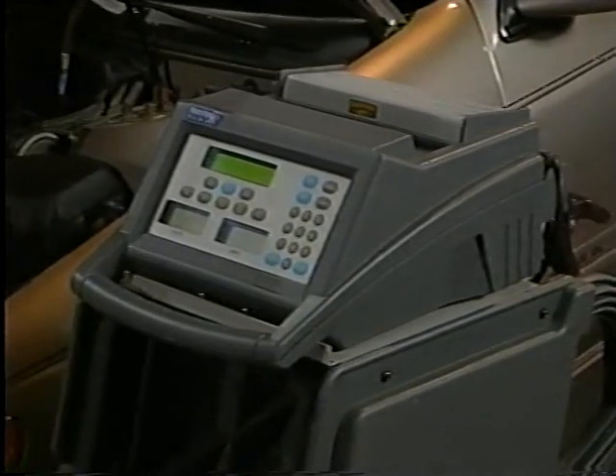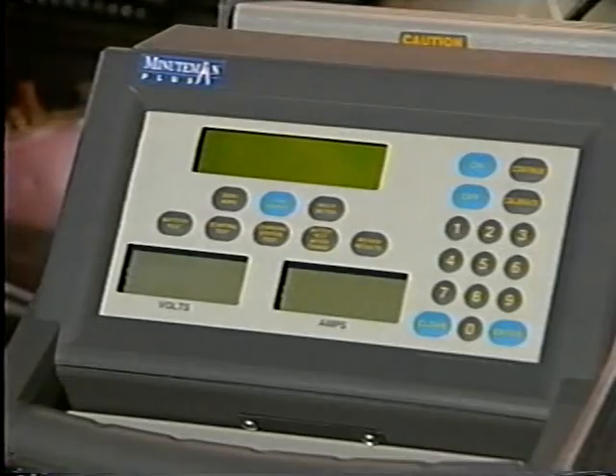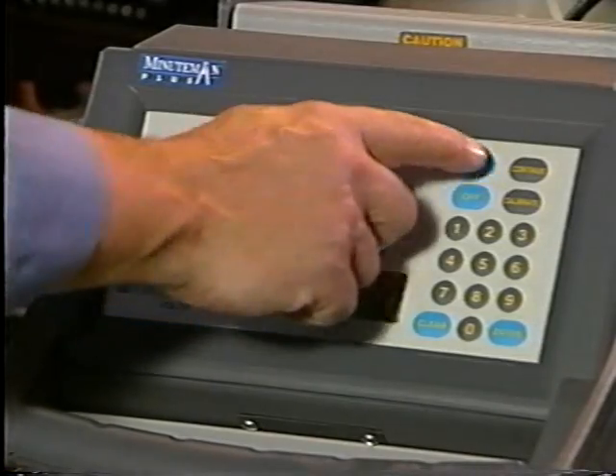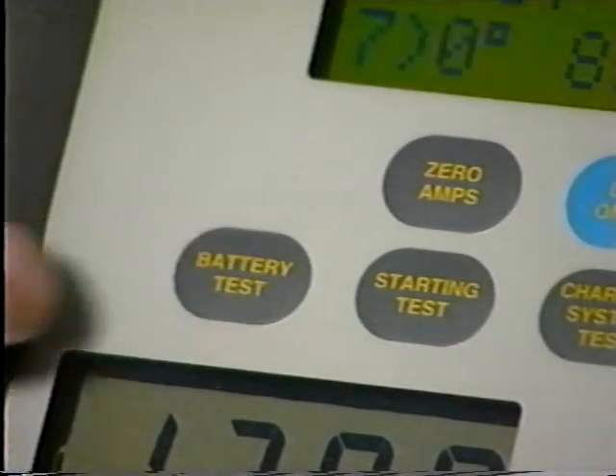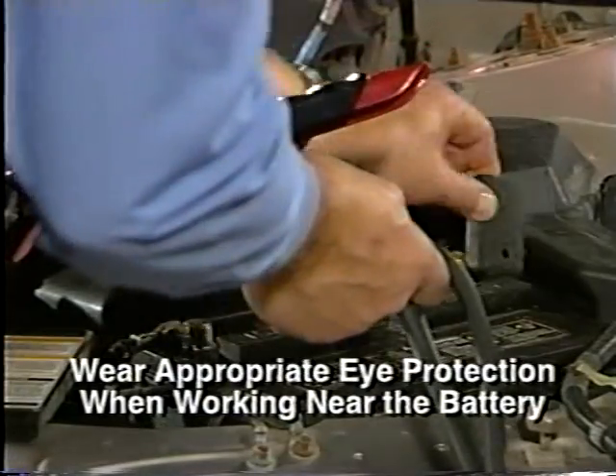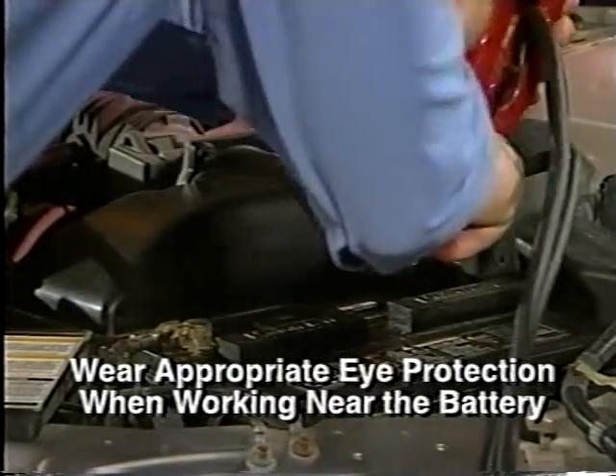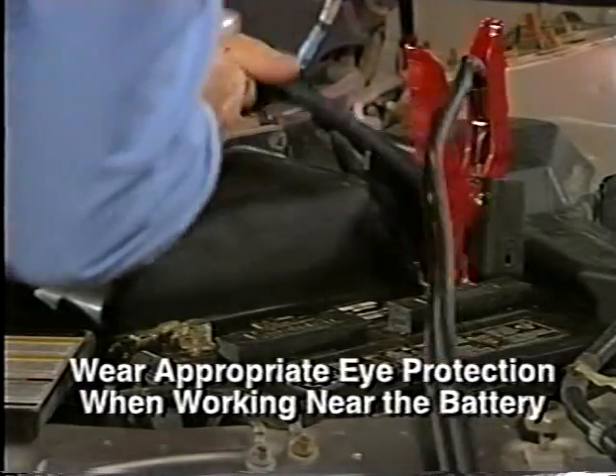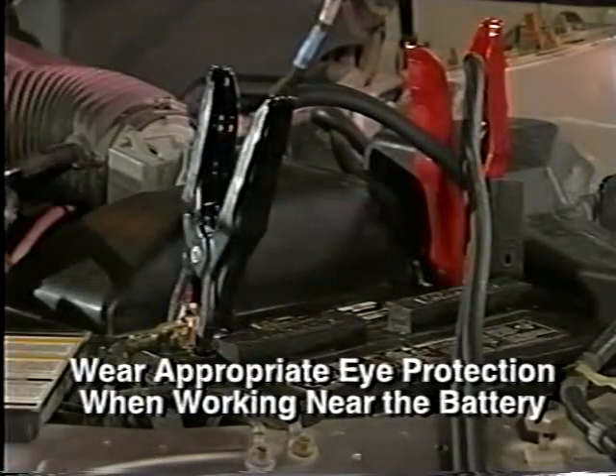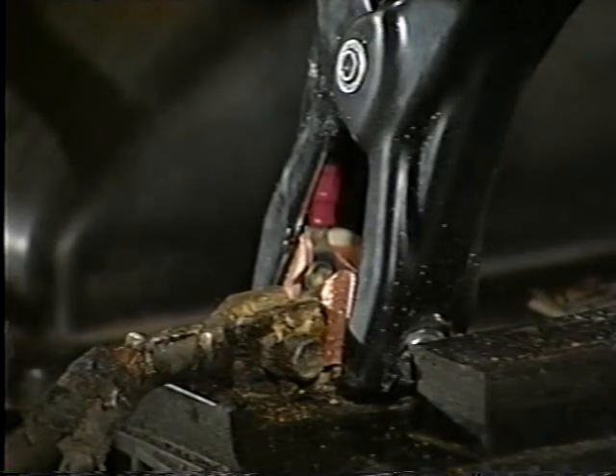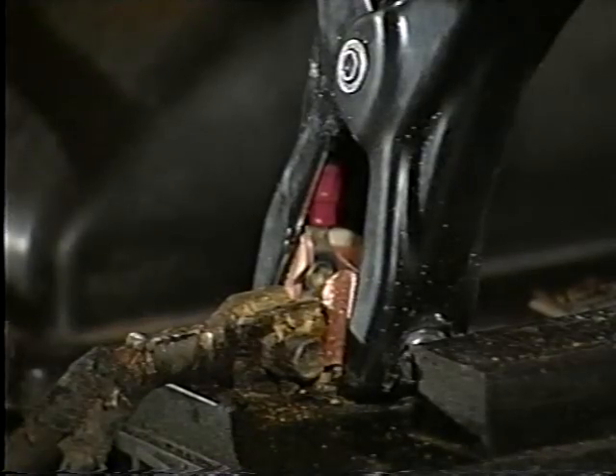OTC's Minuteman Plus quickly verifies the condition of the battery without first having to charge the battery. That's because the Minuteman has been specially designed to accurately test batteries that are partially discharged or fully charged. To run the battery test, simply turn the unit on and select Battery Test. Next, you'll need to connect the battery load clamps. Attach the red clamp to the positive battery terminal and the black clamp to the negative battery terminal. Remember, do not connect the black clamp to any other ground.